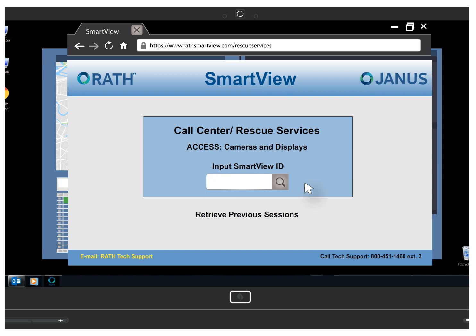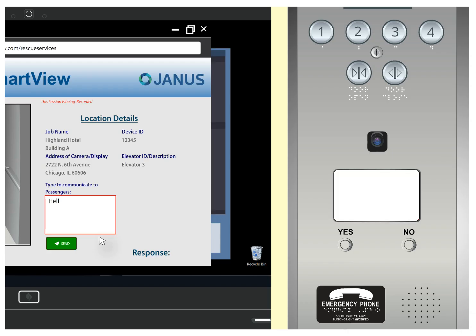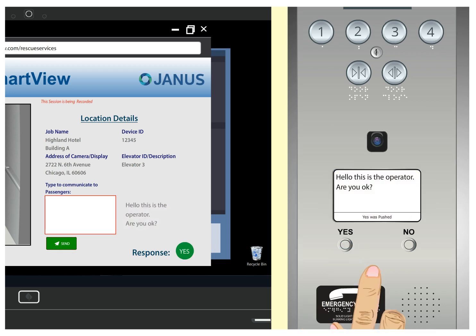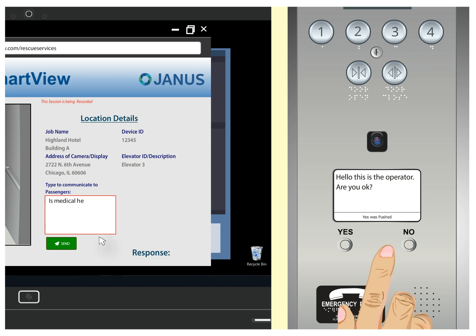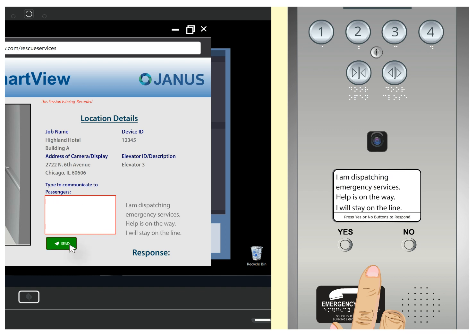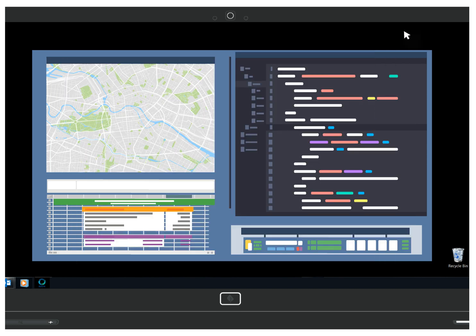They will type in the unique ID for that elevator, which activates the camera so they can view the interior of the elevator. Upon seeing passengers and not receiving a verbal response, a message will be typed on their computer that will display on the LCD screen in the car. Once the monitoring company sends a message, it will remain static until a new message is sent, and the passengers can reply with yes and no responses. When rescue services are dispatched, the monitoring company must send a message stating "Help is on the way." Once help has arrived, the monitoring company disconnects the call by closing the SmartView software.